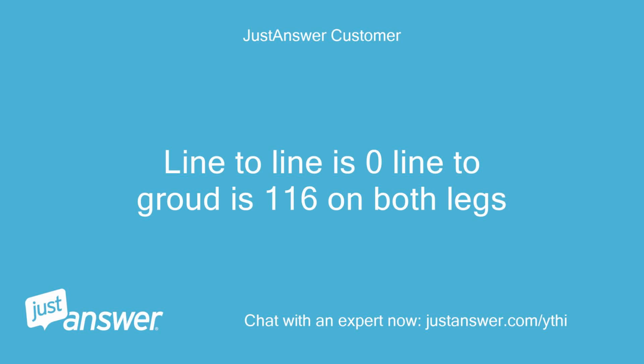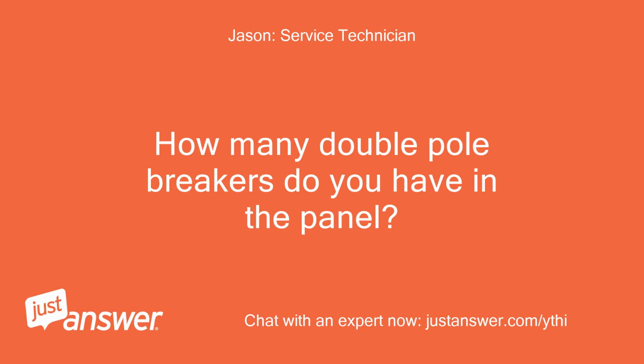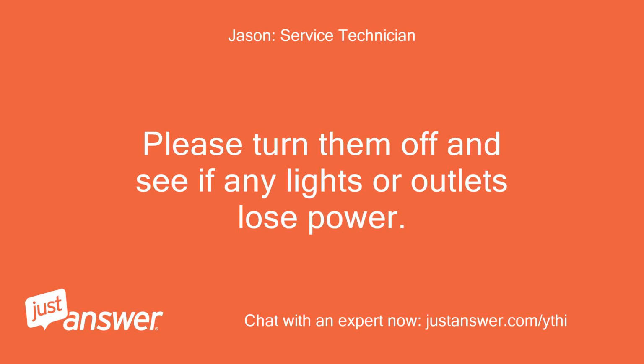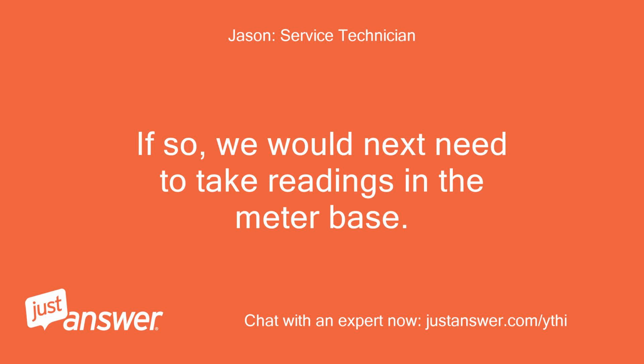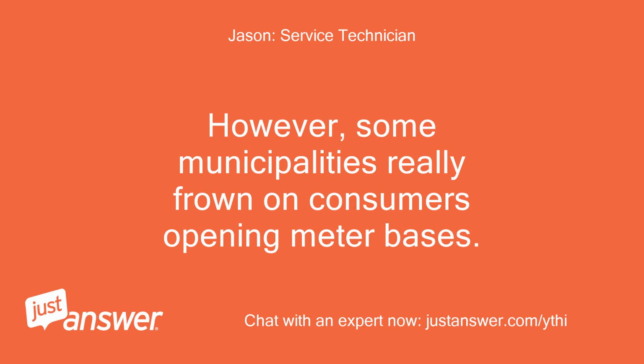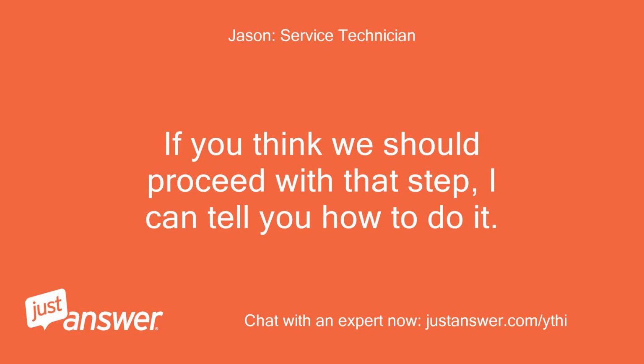Line to line is 0, line to ground is 116 on both legs. How many double pole breakers do you have in the panel? Please turn them off and see if any lights or outlets lose power. If so, we would next need to take readings in the meter base. However, some municipalities really frown on consumers opening meter bases. If you think we should proceed with that step, I can tell you how to do it.